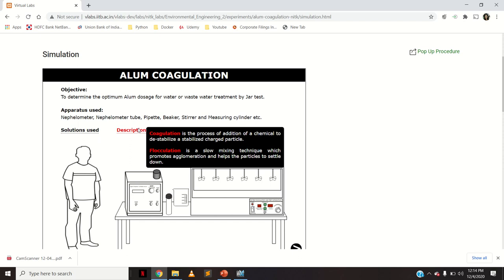Coagulation is the process of addition of a chemical to destabilize stabilized charged particles. Addition of alum leads to coagulation. Flocculation is the slow mixing technique which promotes agglomeration and helps the particles to settle down. When alum is added to water, the stabilized charged particles become destabilized, come together to form larger particles called flocs — that formation is called flocculation — and because of their increased size, they settle down by gravity.